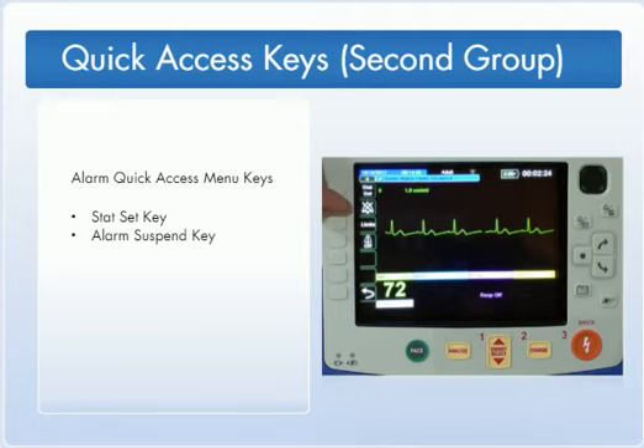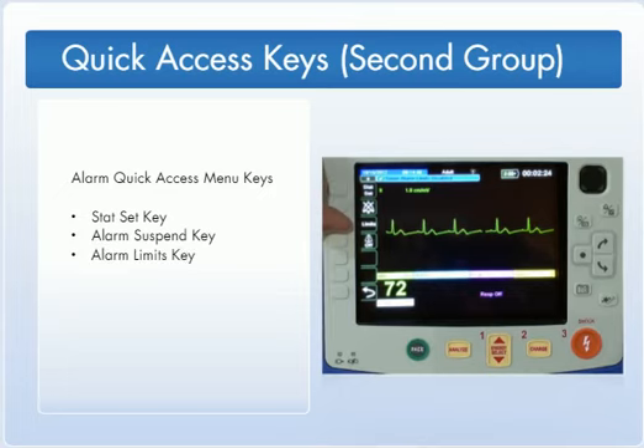During an alarm suspension, the window displays an alarm suspension timer at the top of the display next to the message area. The Alarm Limits key allows the user a fast, global look at all alarm parameters. It also shows an on-off indicator. The user may manually set alarm values in the Limits menu or in the individual parameter menus accessed from the main screen.